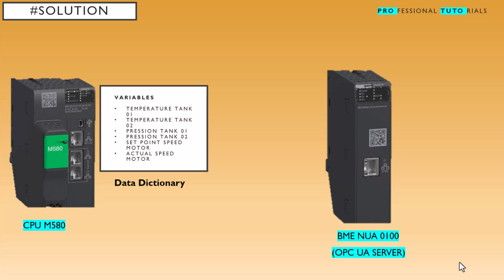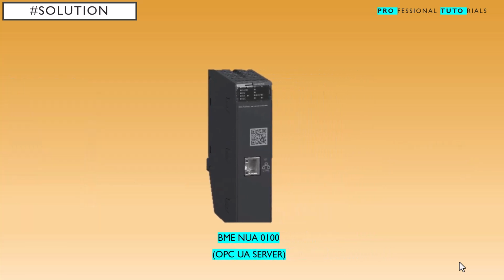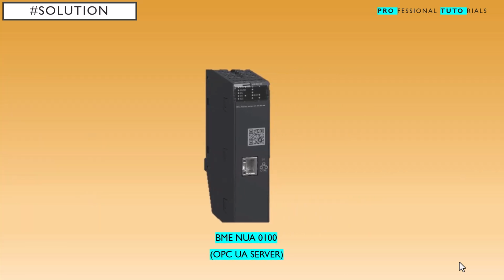Also, the BMENUA module has 2 Ethernet ports, one on the backplane, the other is the front port. So, it accesses the Data Dictionary through its backplane port, and then communicates with SCADA through its front port. Typically, SCADA, or the control network, should be separated from the CPU, or device network, for security reasons. That's why the 2 Ethernet ports of the NUA module are not in the same range.